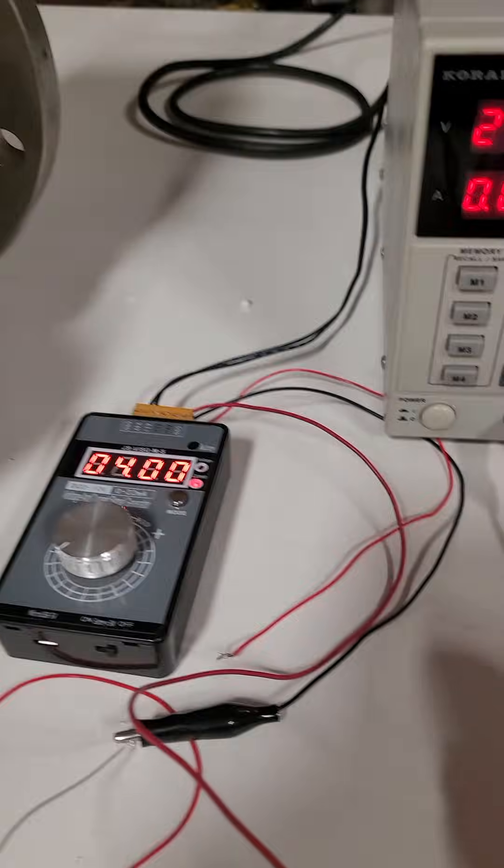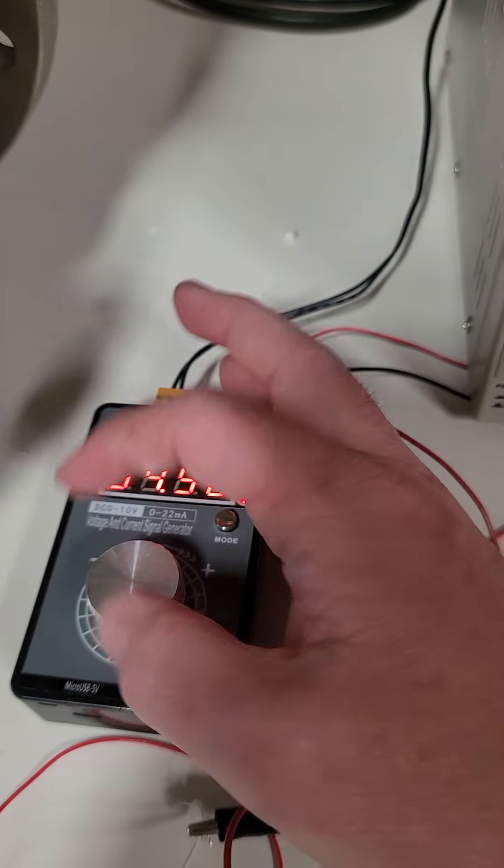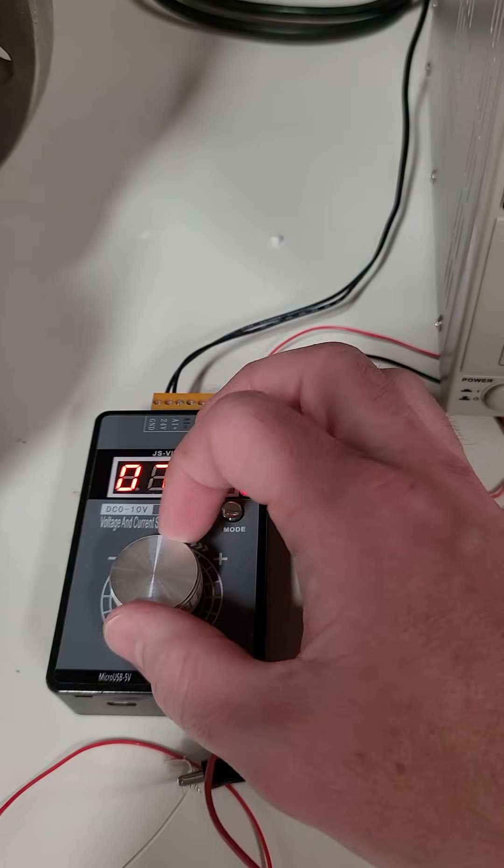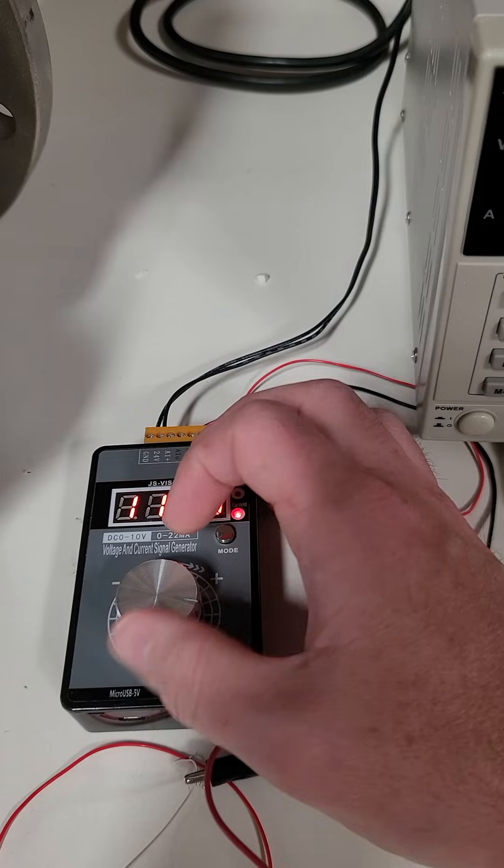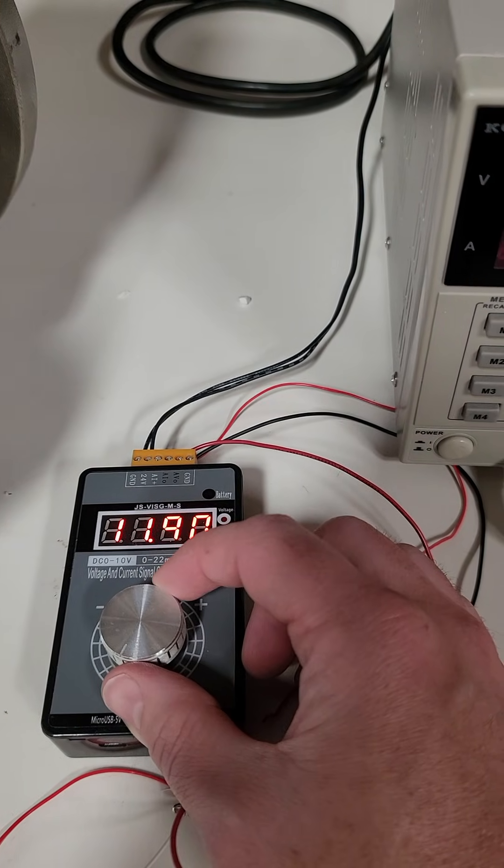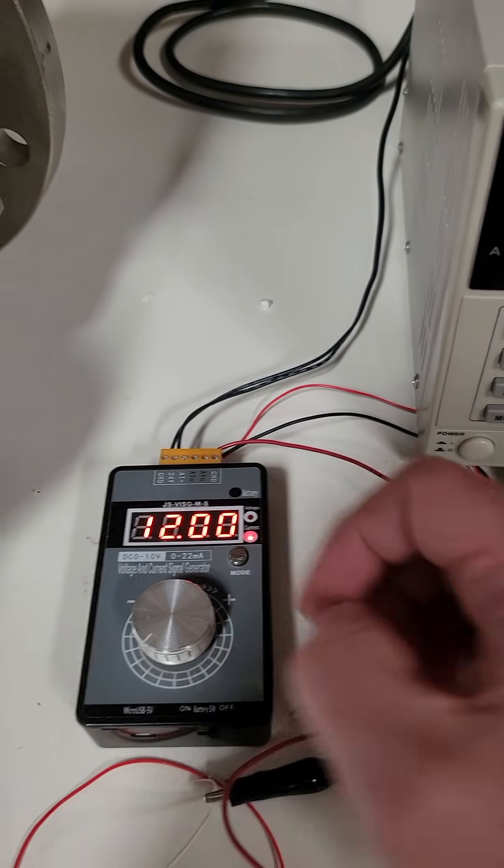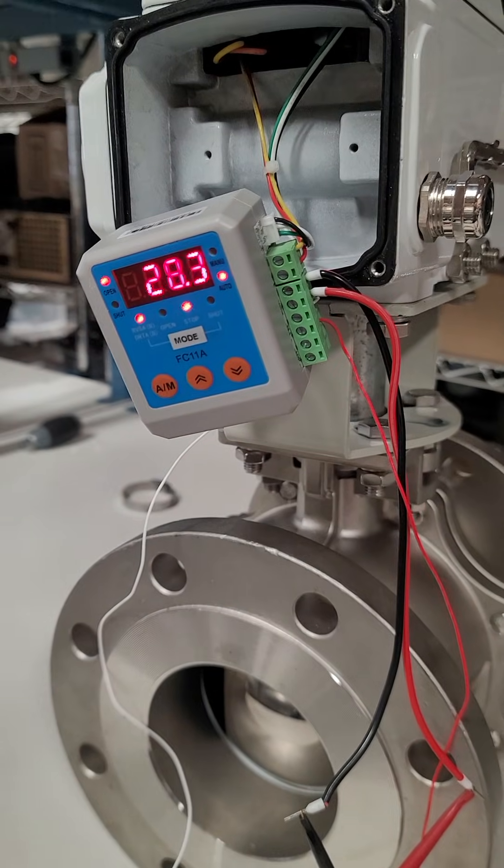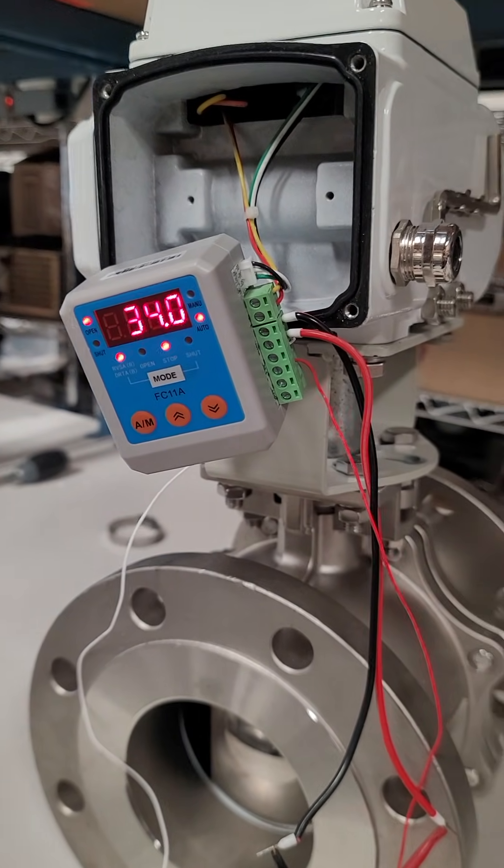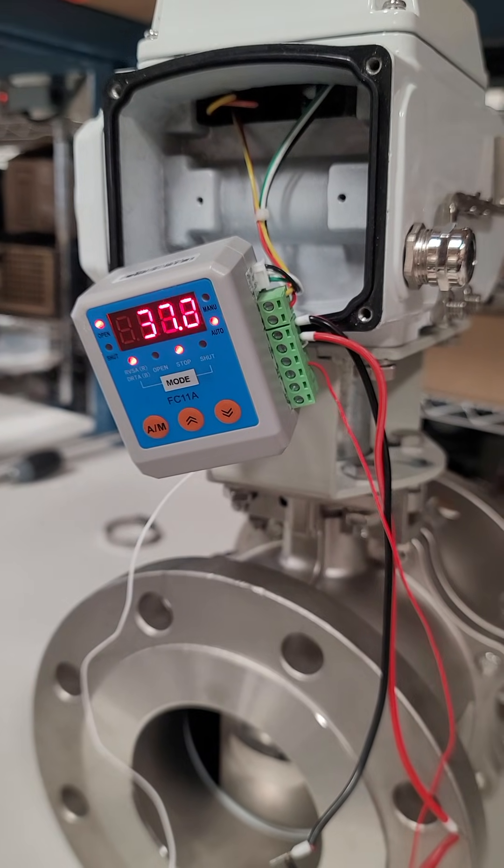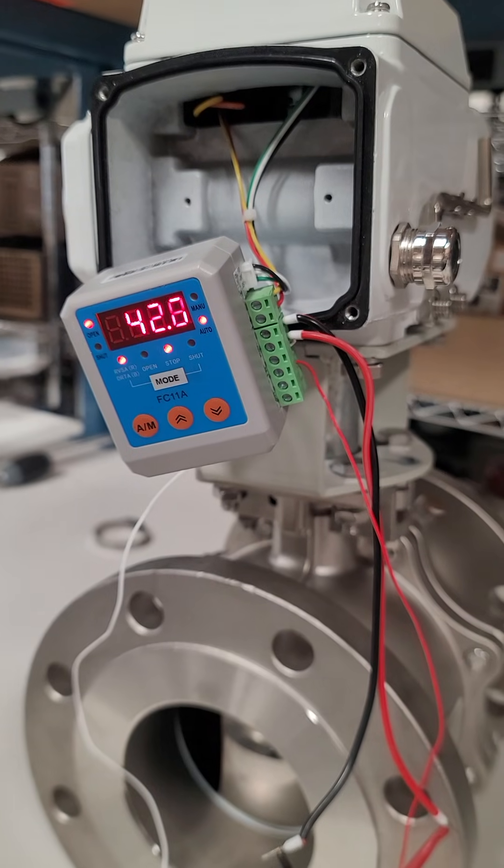Now we're going to increase the 4 to 20 milliamp reading. Let's do half open, so that would be 12 milliamps, and you can see it will go to 50%.